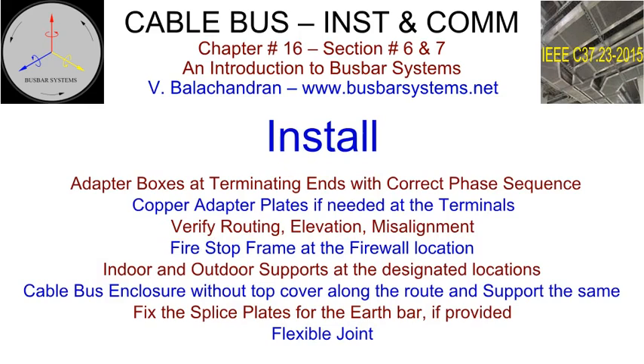Install the adapter boxes at the terminating ends of the equipment. Confirm the phase sequence of terminals. Install the copper adapter plates, if needed and provided, at the terminals of the equipment. Verify the routing, elevation, and note the discrepancy, if any. Make-up piece for length and misalignment may be consolidated at the outdoor end of the termination. Install the fire stop frame at the firewall location. Install the indoor and outdoor supports at the designated locations.